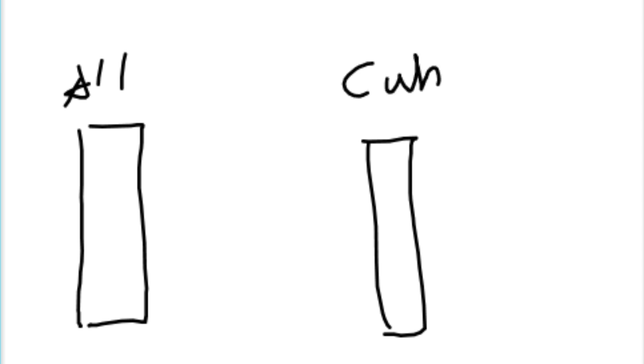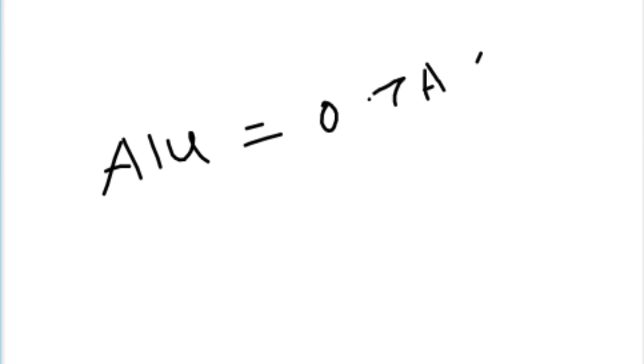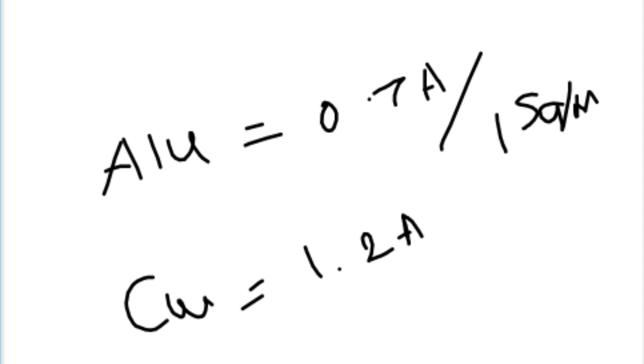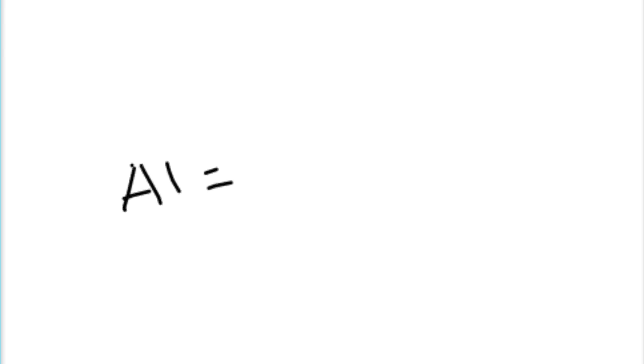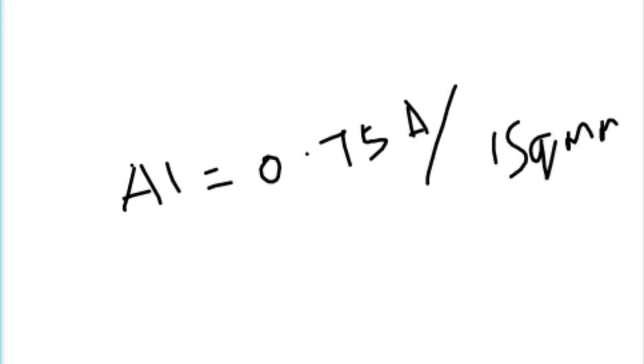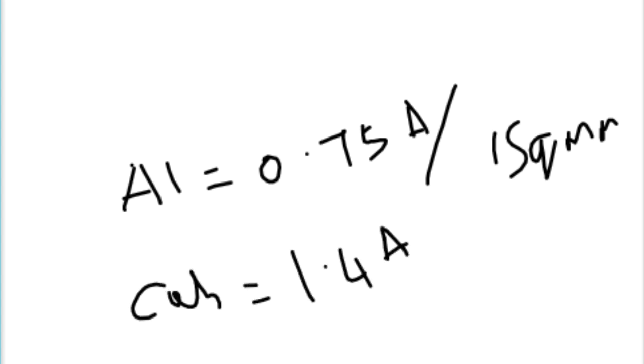So basically about the copper part. The aluminum bar has a current carrying capacity of 0.7 amps per one square mm, and the copper bar has a capacity of 1.2 amps per one square mm. So for the aluminum bar, the rating is 0.75 amps per one square mm, and for the copper bar, the rating is 1.4 amps per one square mm. So based on this, you choose the appropriate bus bar size.